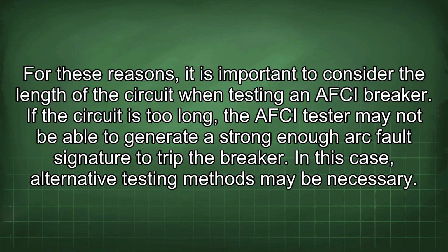For these reasons, it is important to consider the length of the circuit when testing an AFCI breaker. If the circuit is too long, the AFCI tester may not be able to generate a strong enough arc fault signature to trip the breaker. In this case, alternative testing methods may be necessary.